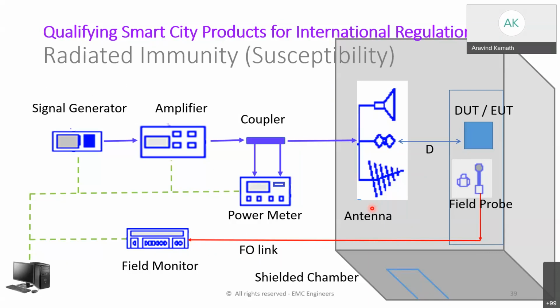From the signal generator, I am going to amplify the signals. The signals will go to a directional coupler. The directional coupler is for tapping purposes. You can tap it for a power meter. The other signal will directly go to the antenna, and you will radiate on your equipment. Depending on the frequency of operation, the antennas will be different for different frequencies. The equipment is going to get exposed to radiation, and there is a chamber here. So you do the radiated emission and radiated immunity tests inside a shielded chamber.